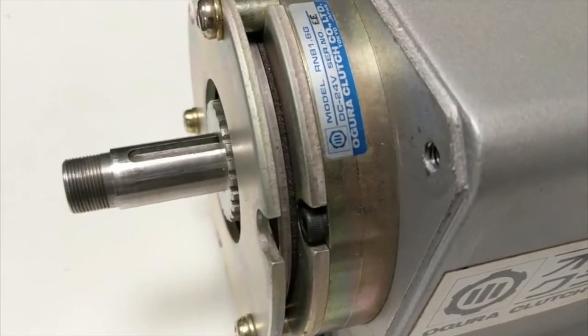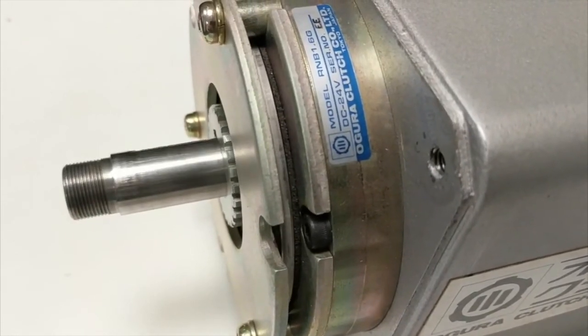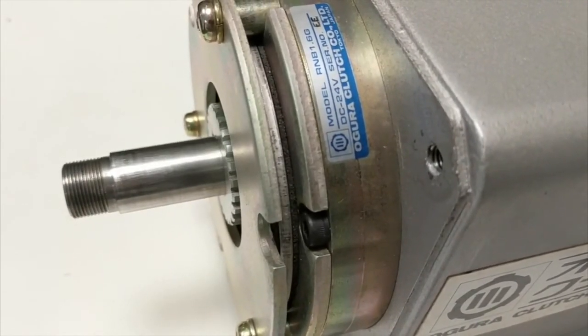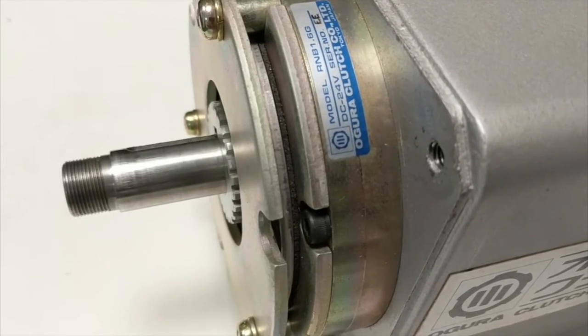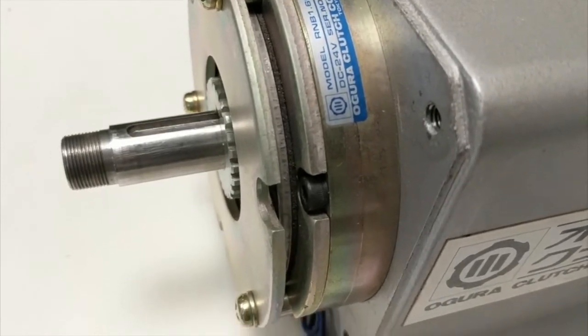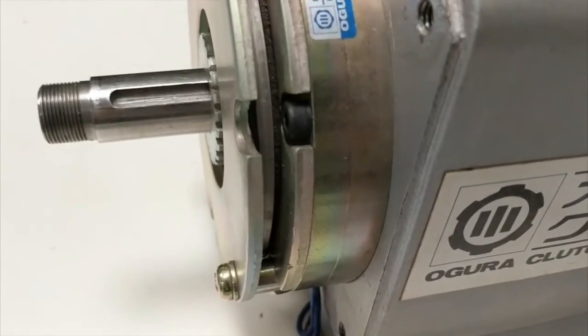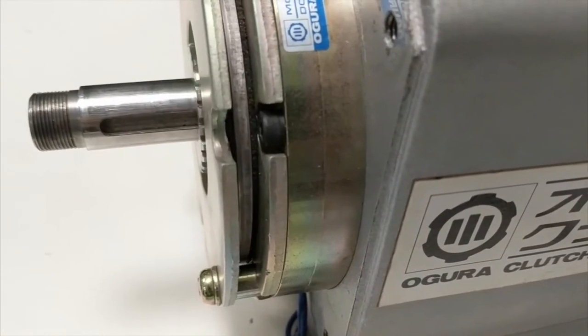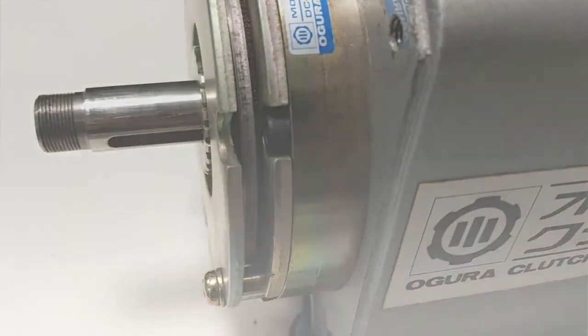When the brake is disengaged, there should be almost no noise. If noise is coming from rubbing, the hub or shaft may be misaligned. If the sound is more of a metallic sound, the hub may be contacting the pressure plate during rotation.